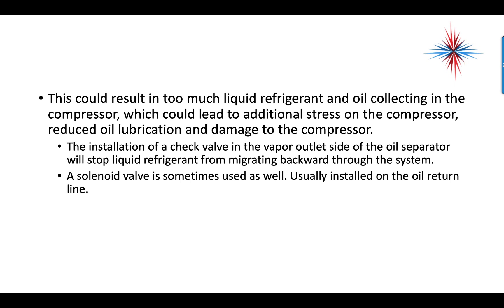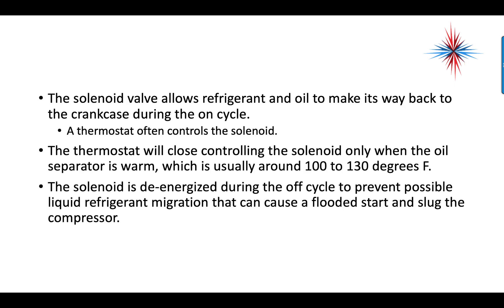A solenoid valve is sometimes used as well, usually installed on the oil return line. The solenoid allows the refrigerant oil to make its way back to the crankcase during the ON cycle. The thermostat will control the solenoid only when the oil separator is warm, usually around 100 to 130 degrees. The solenoid is de-energized during the OFF cycle to prevent possible liquid refrigerant migration that could cause a flooded start or slug the compressor.